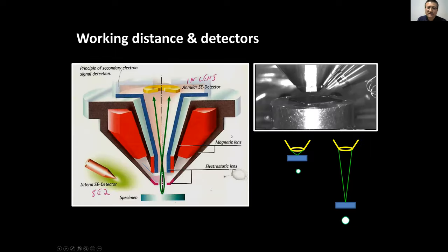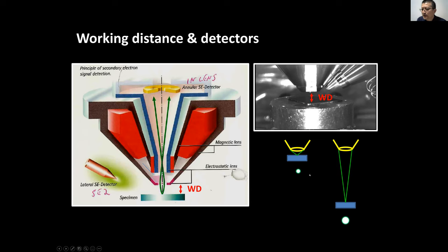What is working distance? It's the distance between your sample and the final lens in the SEM column. When you change the sample height — closer or farther away — the beam cross-section changes. When your sample is very far, even if you focus the beam onto it, the beam size is actually bigger. That's why the first thing you want to do when loading a sample is move it up close to get a good image.